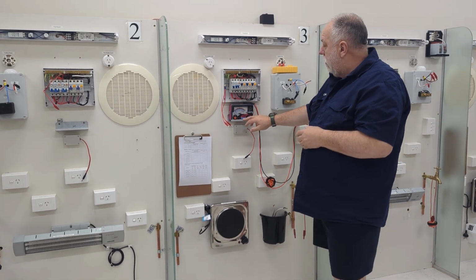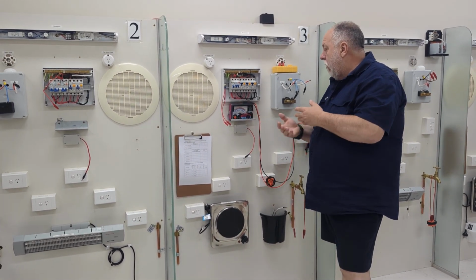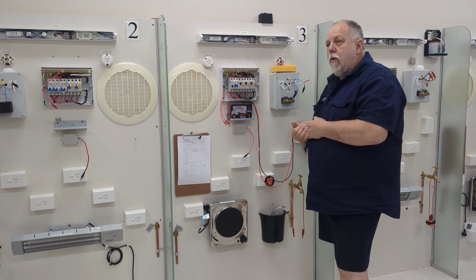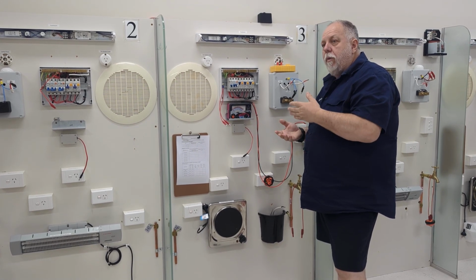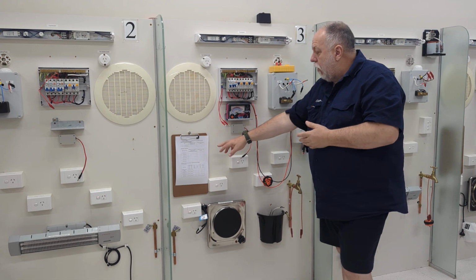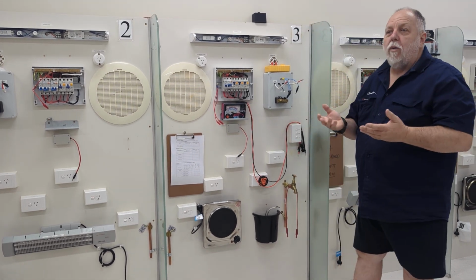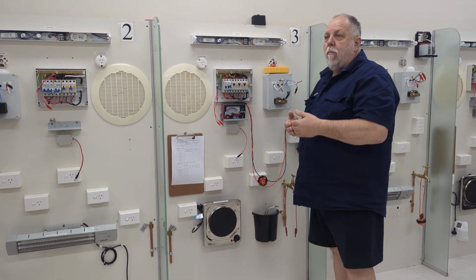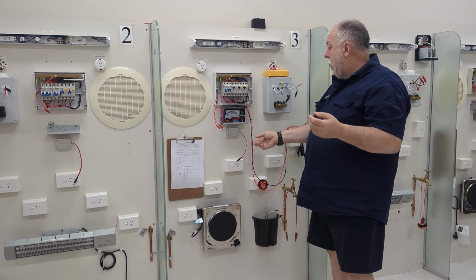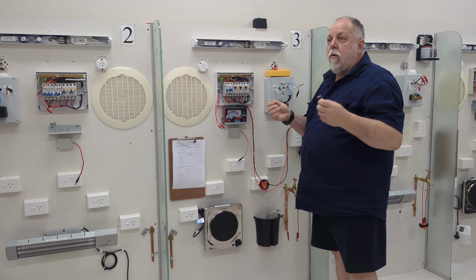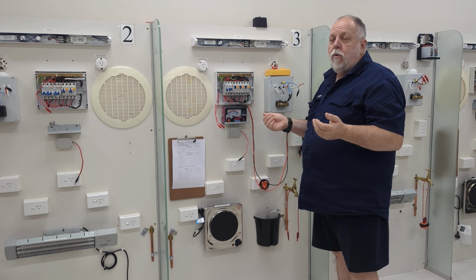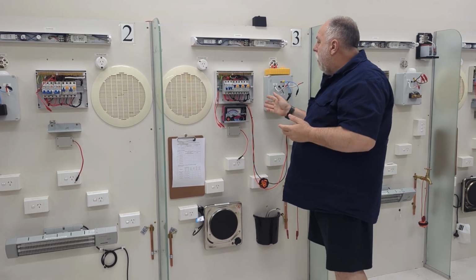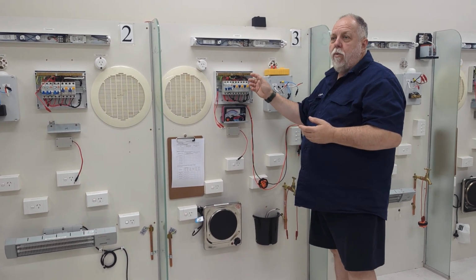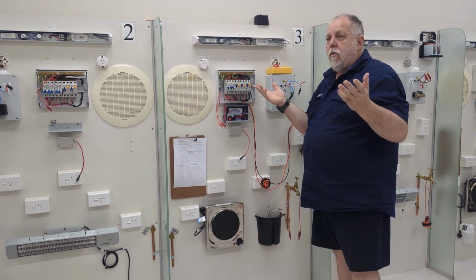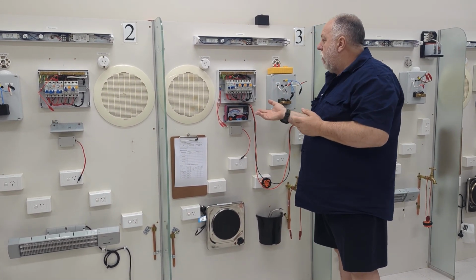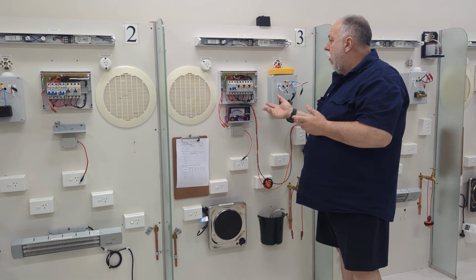The other thing is the difference between the two. When we do anything in the blue, it's continuity. Continuity is for things like when we test the mains, okay, so one of the requirements down here is continuity of the mains. We don't need to pump 500 volts through it, we only need to pump just a couple of volts, but the continuity through it to make sure it goes from A to B. We would use a trailing lead for that. In part of the SWP now, they're asking you to establish the earth with a trailing lead. And people, it looks like it's a whole new language to them, but really when you do testing of an insulation, you use it more than the earth.